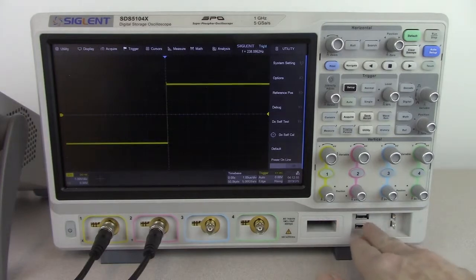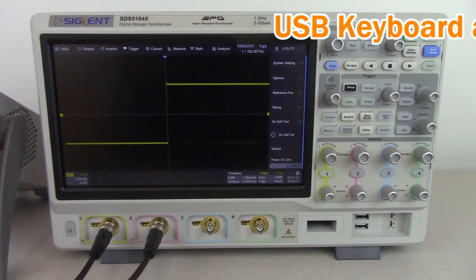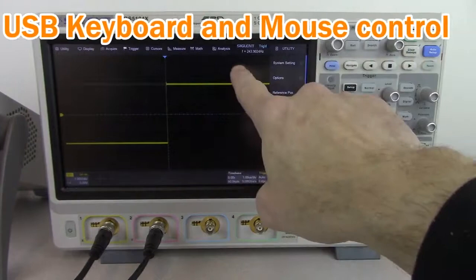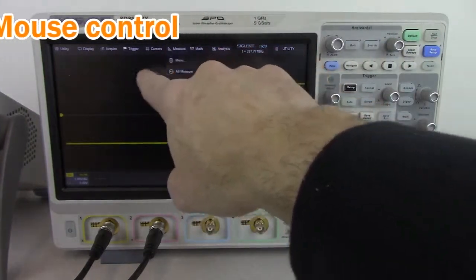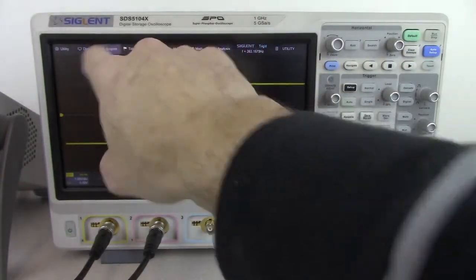There's also 2 USB ports on the front that can be used with a USB stick for a memory device to save images and data, as well as saving setups. And this scope also supports keyboard and mouse control. So we could connect a keyboard here and be able to type in labels, or use a mouse very similar to our finger. This also supports touchscreen. So you can see some of our pictures or some of our menu-driven items here.